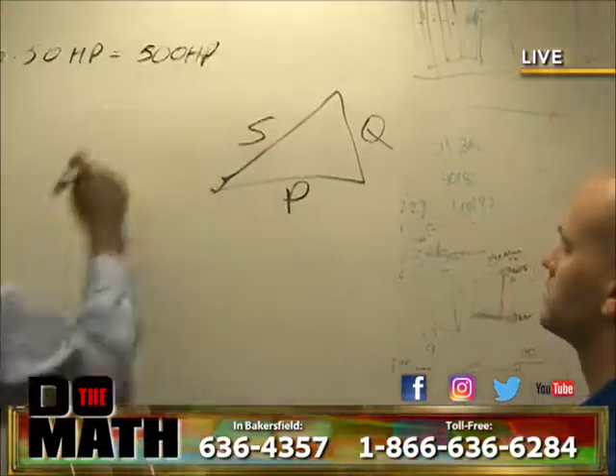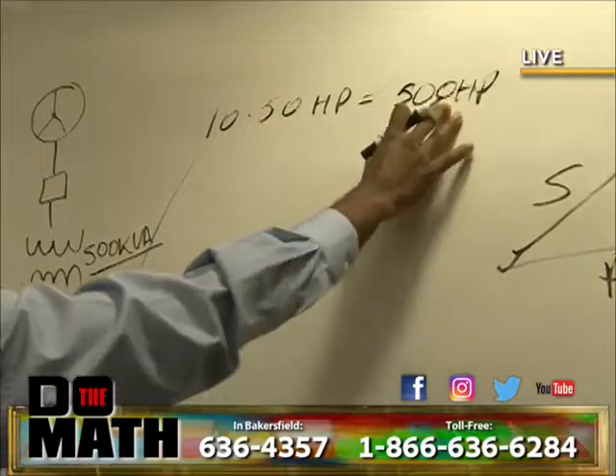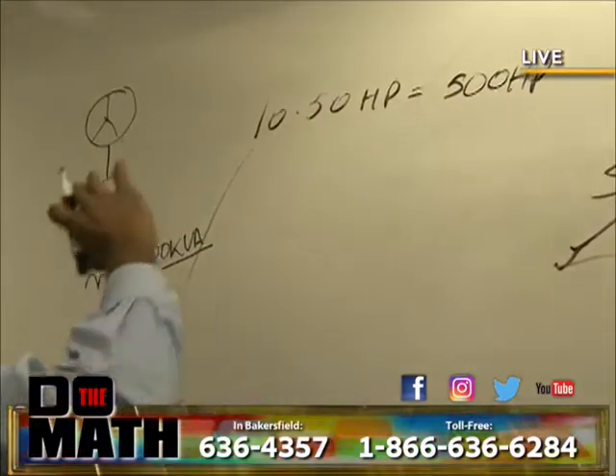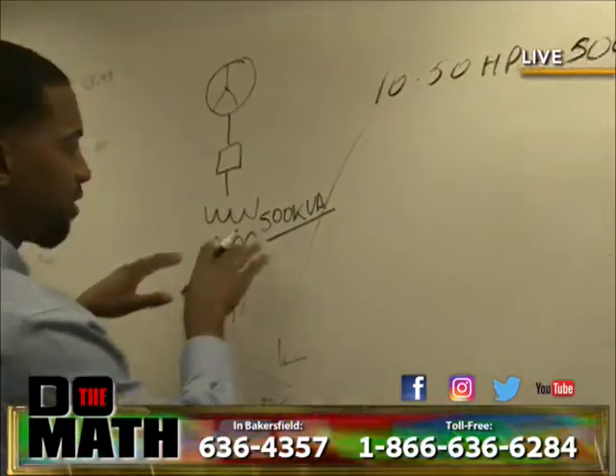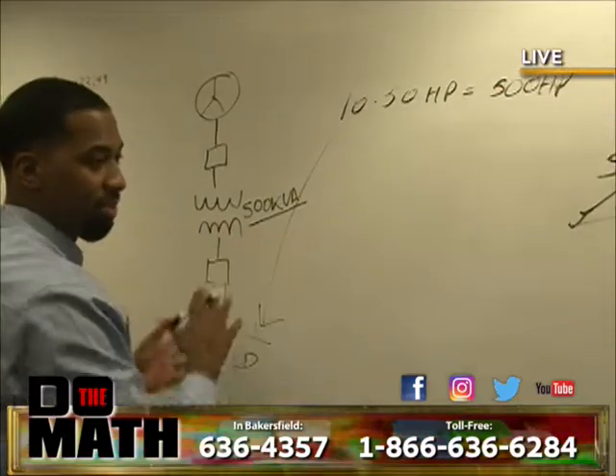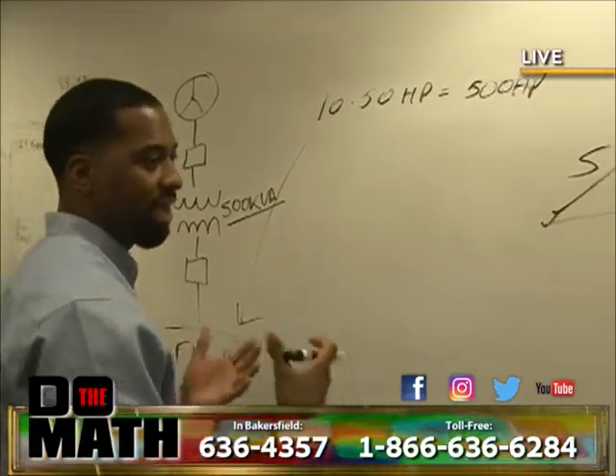That is correct. All right, so now we have to convert this, because horsepower and kVA are two different units, so we need to get this into amps, and eventually transform the kVA into amps as well, and compare whether we have sufficient capacity to add these new loads.